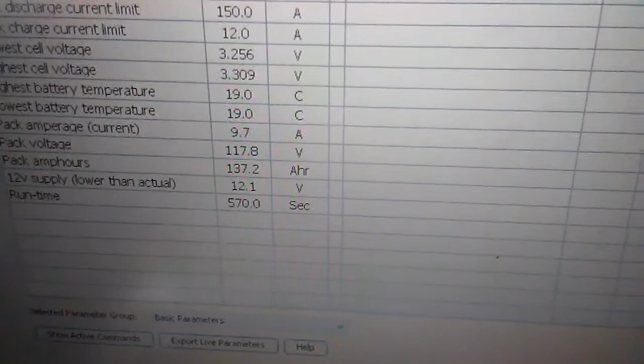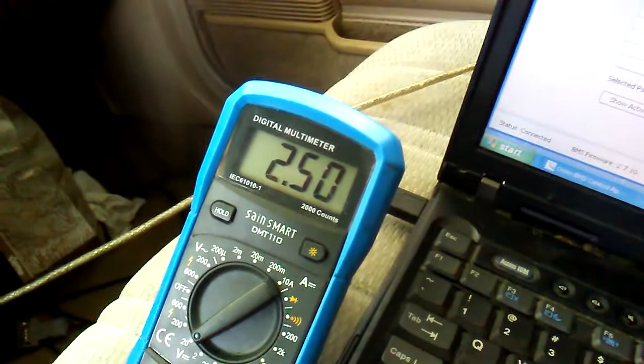If we go to this screen, you can see that if I rev the motor, that's a discharge and it's registering as positive current. But if I look at this 1 to 5 volt signal coming out of it, the voltage goes down as I rev the motor.